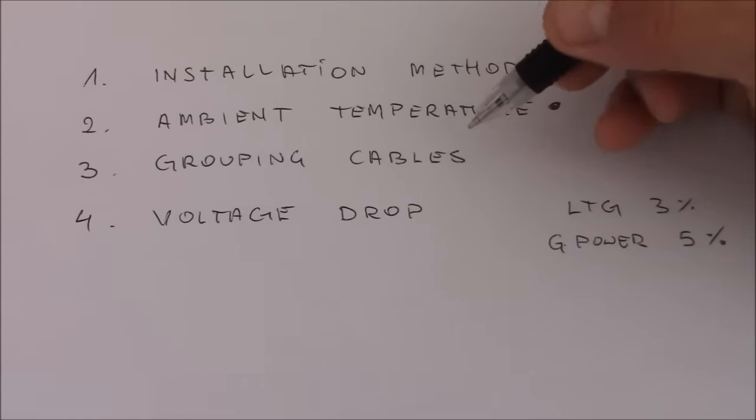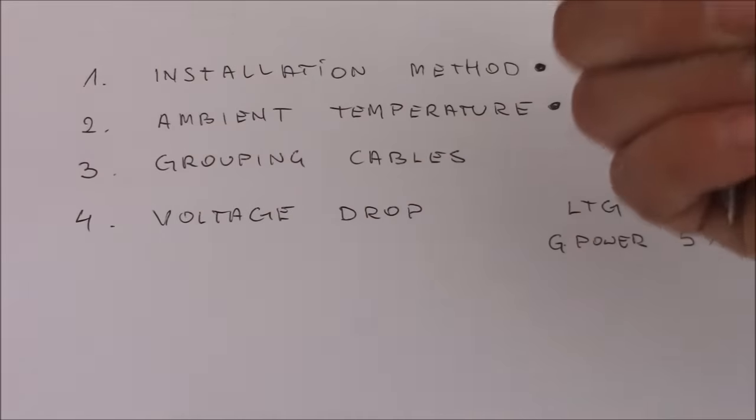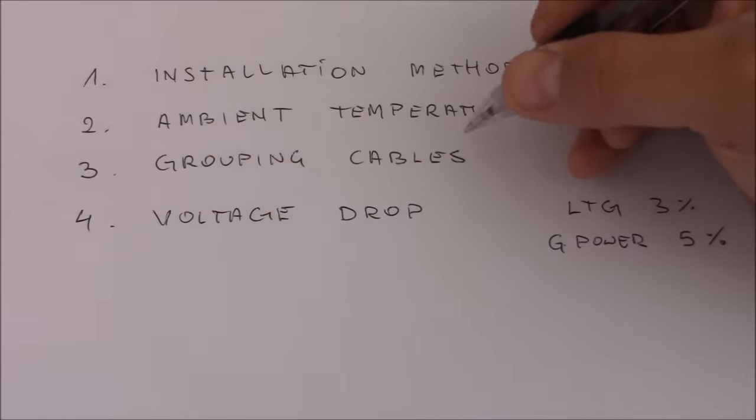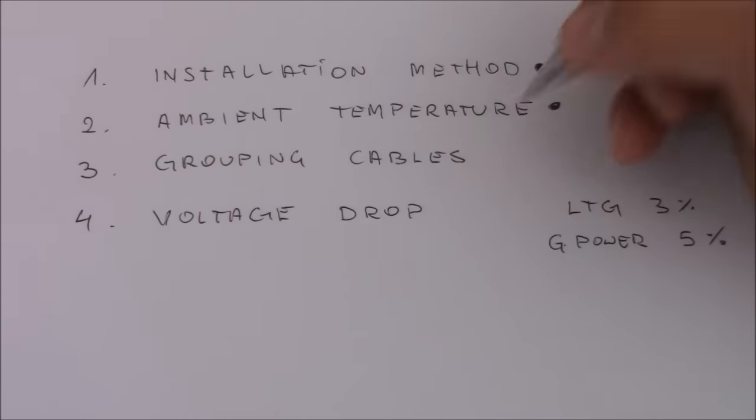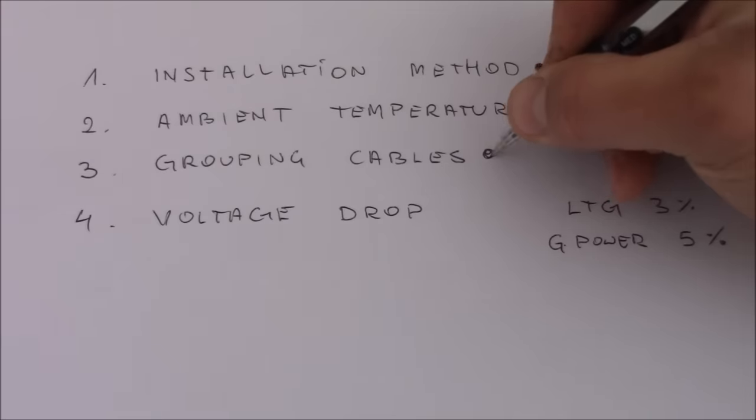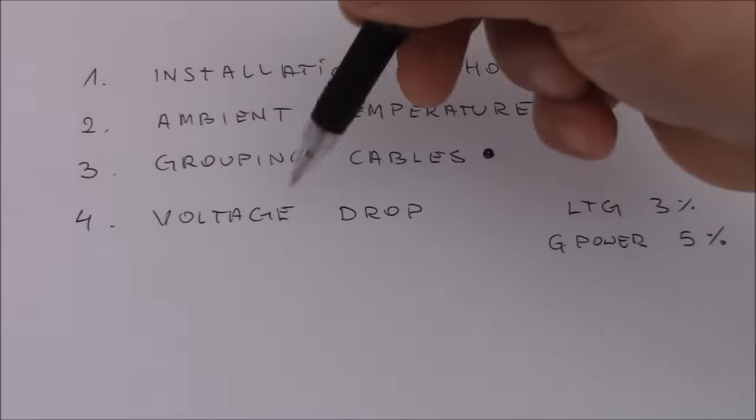The grouping cables as well, it's number three. So basically when you install let's say five cables in a bunch somewhere in a wall, they're just warming up. They can't give the heat outside as they're just warming each other. So you need to consider this.